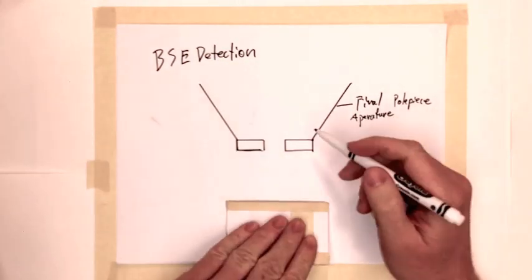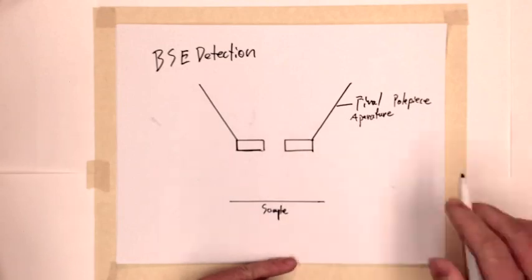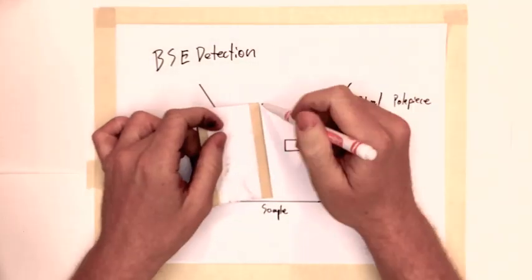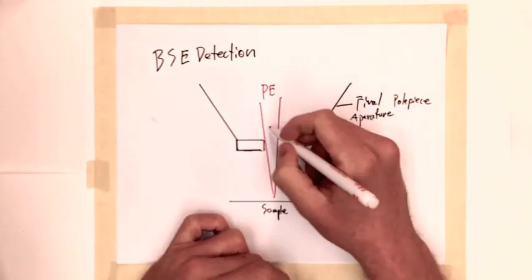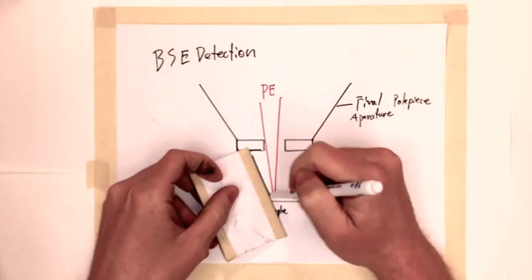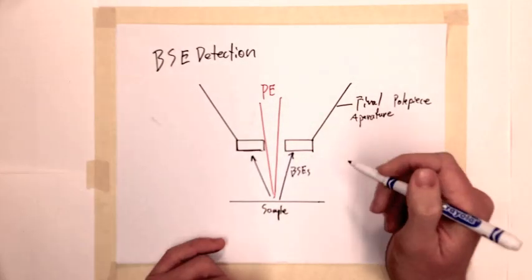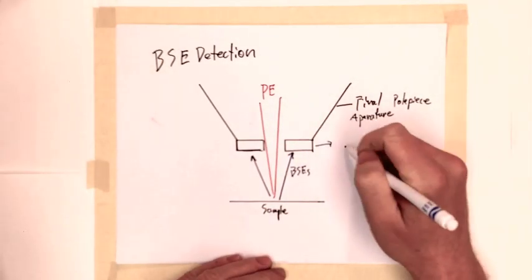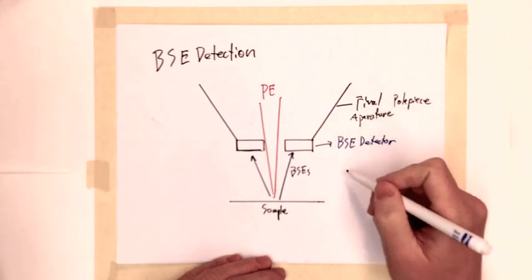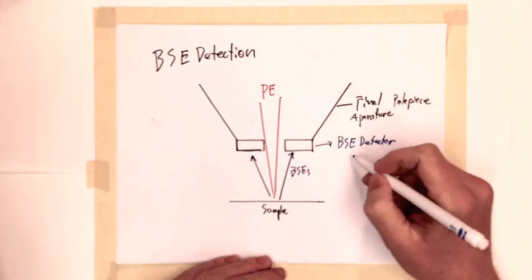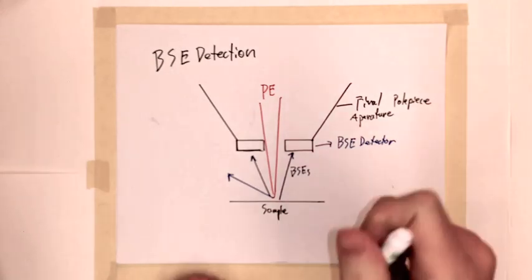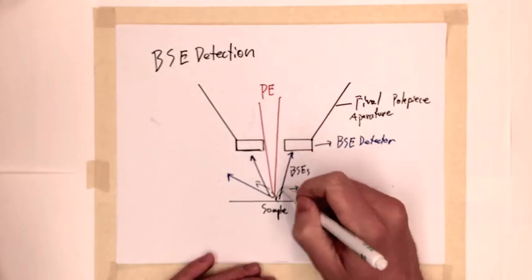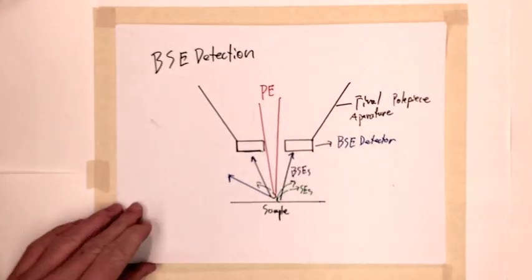The detectors are generally either solid state or scintillating configurations which provide an output response proportional to the electron energy. This implies that backscattered electrons having higher energy will make large contributions to the signal. However, the system will see any electrons that interact with the detector, and the output signal will integrate any number of the possible scattering processes.